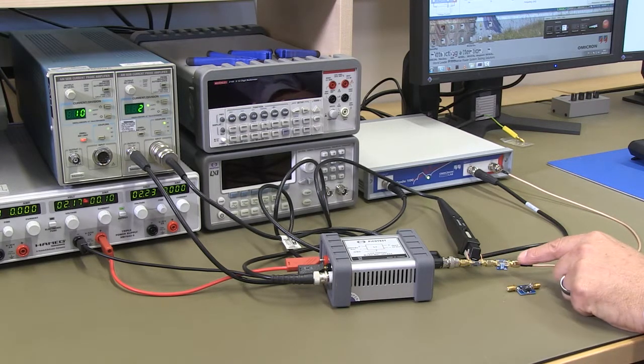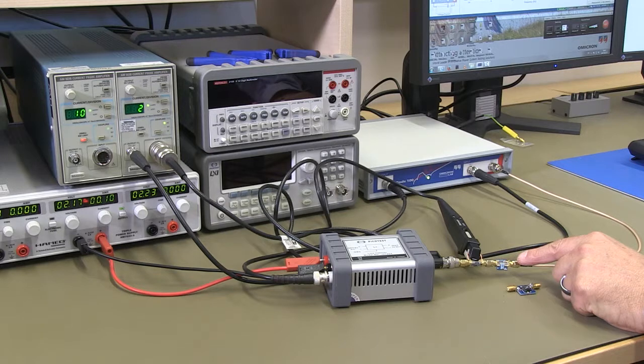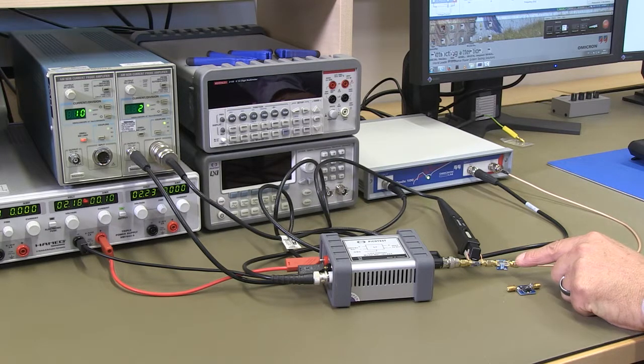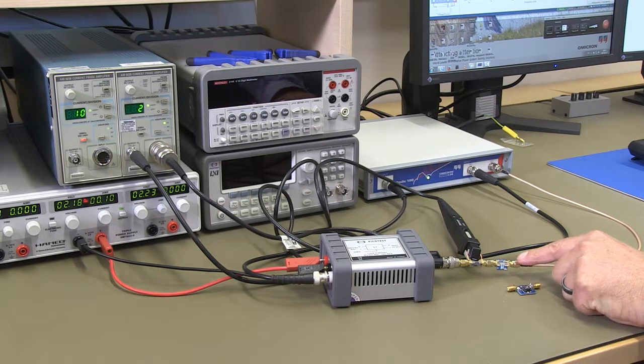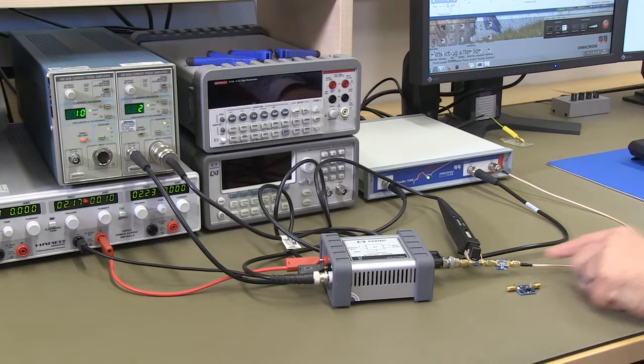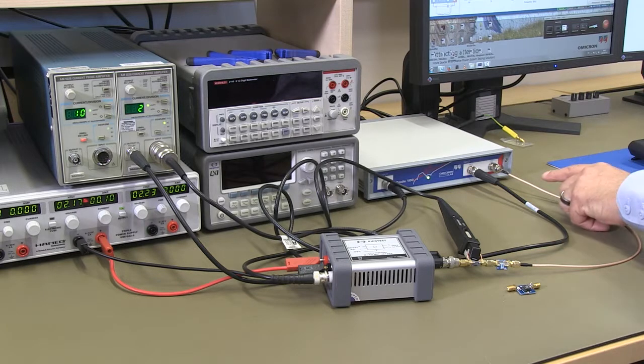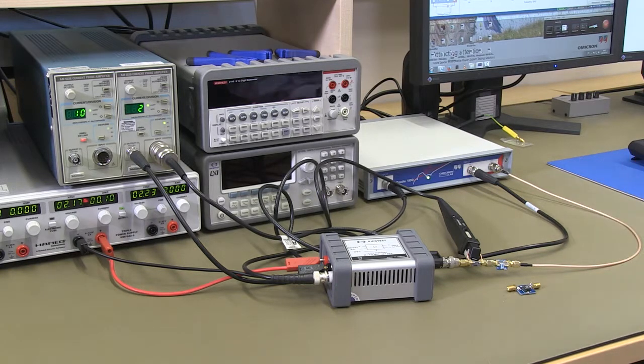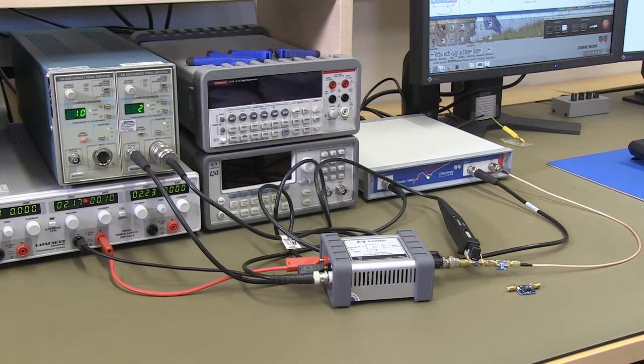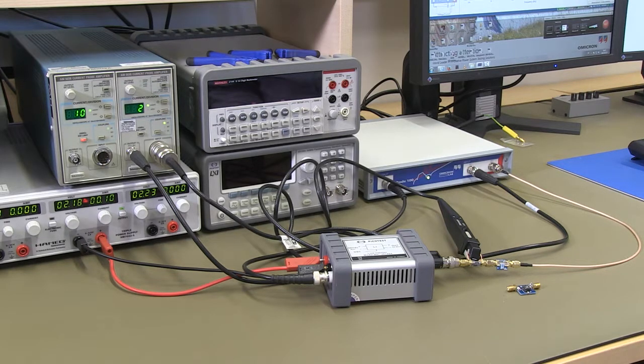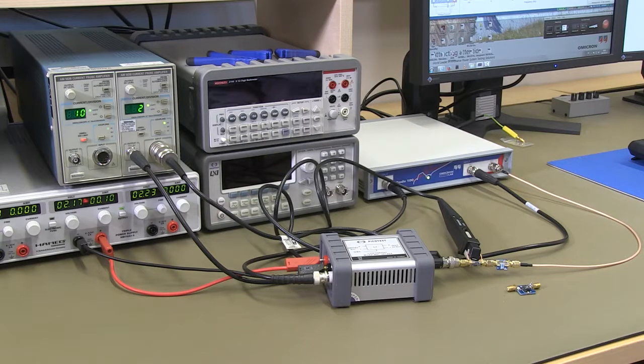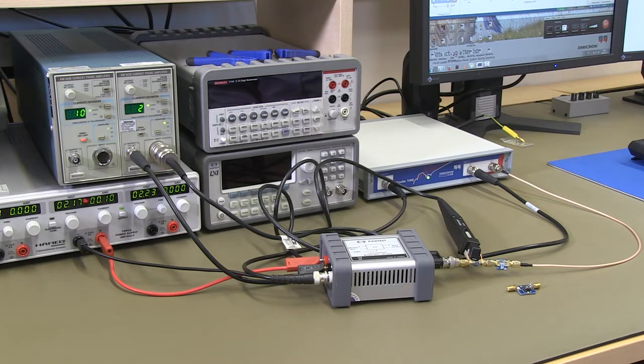For calibration, we have a small 1 ohm resistor and one side of the resistor is used to measure the voltage in channel 2 of the Bode 100. After performing a through calibration, we'll end up with flat response, correcting for all of the imperfections in both the current probe and also the line injector.